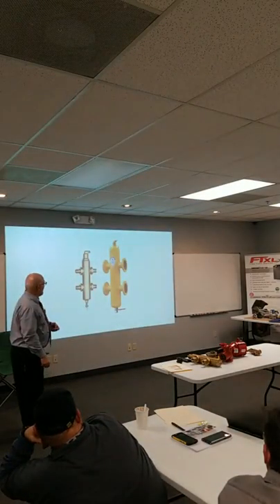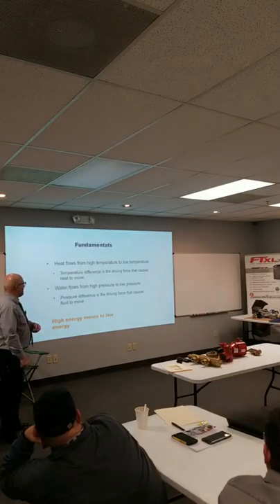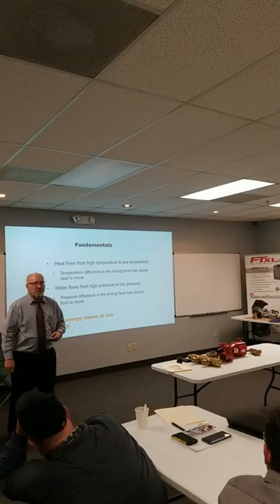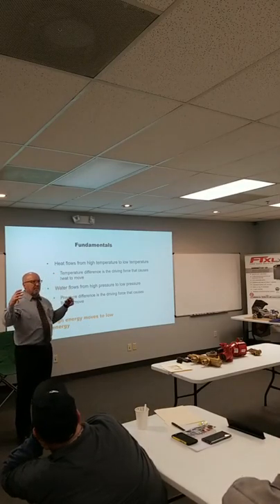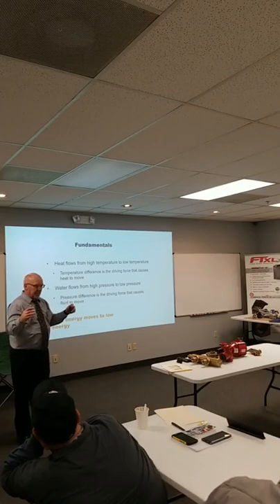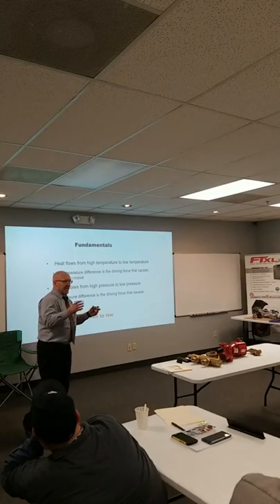Yeah. So the quad, again, eliminates the guesswork of primary, secondary. You need good quality air separation and everything else. Is there any sizing involved with the separator? Yes. So the vessel is larger than the pipe size coming in. You never want to decrease pipe size going into an air separator, any kind of air separator, ever. But a quad, same thing.